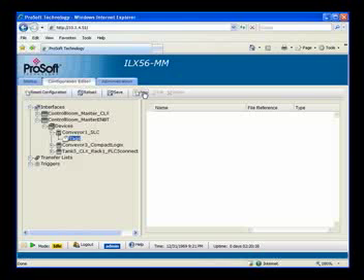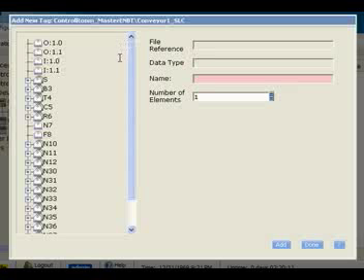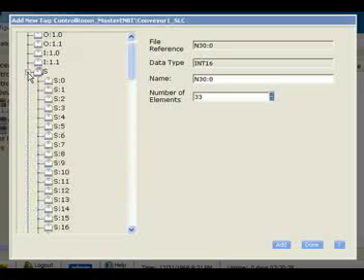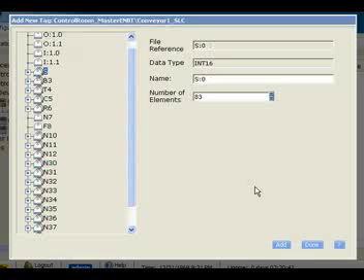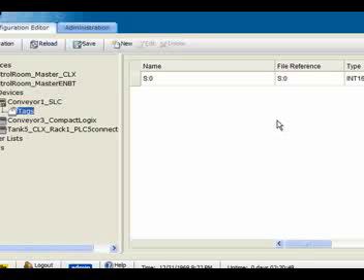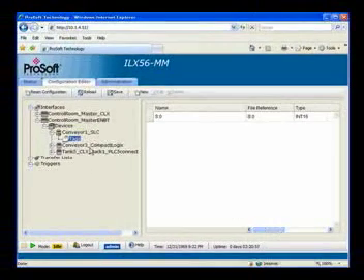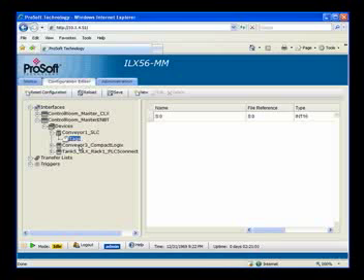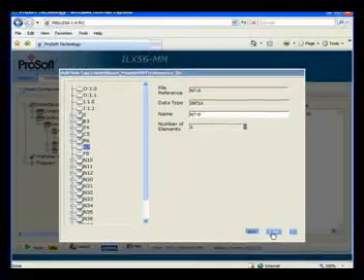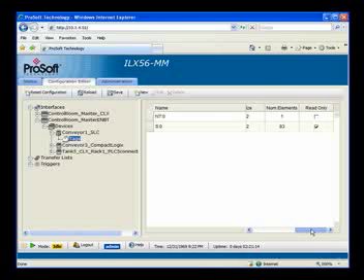Now we will start adding tags. Under my SLC processor I'll click New for New Tags. Once I click New, the SLC will be interrogated and it will return all the tags — or data files — within the SLC. I'm going to select the S0 tags, click Add, and we see the tag has been added. Note that status tags have a read-only attribute. I'll add one more tag: I'll click New again, select the N7 tag, click Add, then Done. Our N7 and S0 tags have been added — that should be good for the SLC.